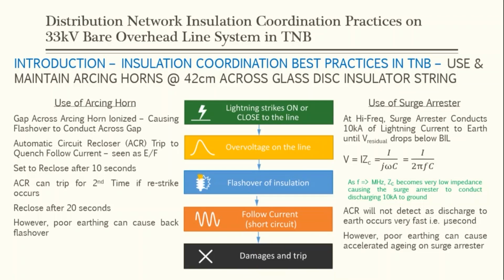But with the use of surge arrestor, the automatic circuit recloser will not detect any earth fault, as the discharge to earth will occur at a very fast rate in the range of microseconds. However, again, poor earthing can cause accelerated aging of the surge arrestor.